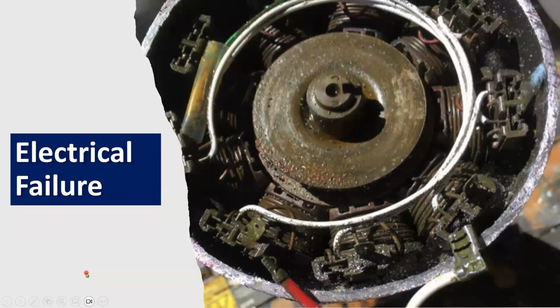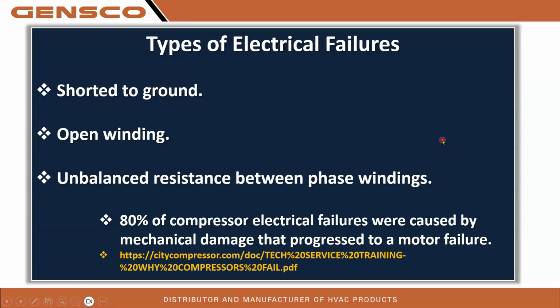Now we'll talk about electrical failures. Obviously, this one looks pretty bad. Types of electrical failures: shorted to ground, most common failure. An open winding, not really common. Unbalanced resistance between phase windings. And to point out, 80% of compressor electrical failures were actually caused by mechanical damage that progressed to the motor failure.